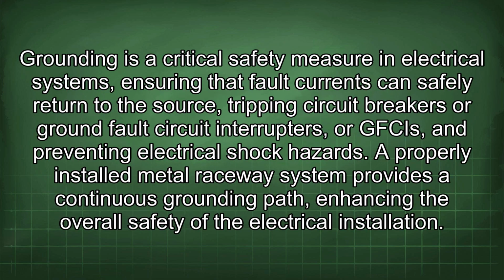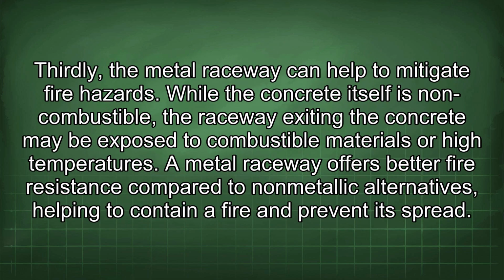Grounding is a critical safety measure in electrical systems, ensuring that fault currents can safely return to the source, tripping circuit breakers or ground fault circuit interrupters, or GFCIs, and preventing electrical shock hazards. A properly installed metal raceway system provides a continuous grounding path, enhancing the overall safety of the electrical installation. Thirdly, the metal raceway can help to mitigate fire hazards. While the concrete itself is non-combustible, the raceway exiting the concrete may be exposed to combustible materials or high temperatures. A metal raceway offers better fire resistance compared to non-metallic alternatives, helping to contain a fire and prevent its spread.